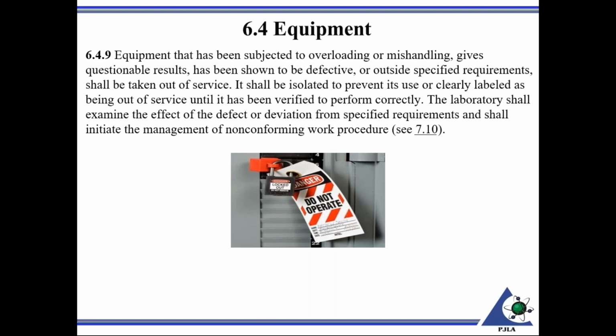The laboratory shall examine the effects of the defect or deviation from specified requirements and shall initiate the management of nonconforming work procedure. Again, section 7.10, nonconforming work. So if equipment was being used when it was determined that it may be operating outside of predefined limits of acceptance, possibly you have to implement the protocol established in section 7.10 there.